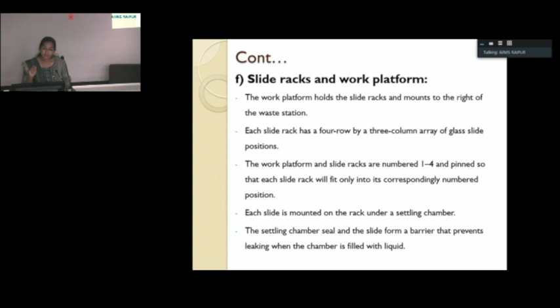Each slide is mounted on the rack under a settling chamber. The settling chamber will seal, and the slide forms a barrier that prevents leaking when the chamber is filled with liquid. At the time when we receive the sample, it is very important to label each centrifuge tube, each sample and each slide. It is done at the same time.